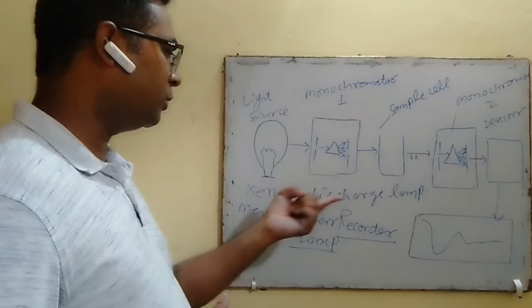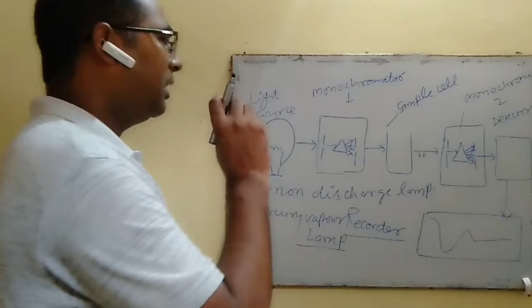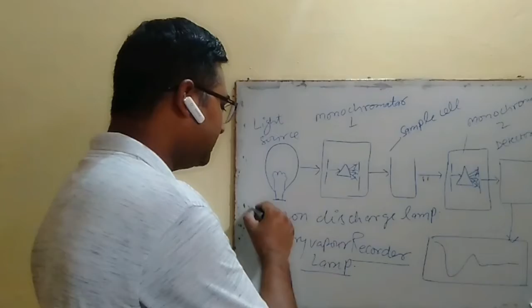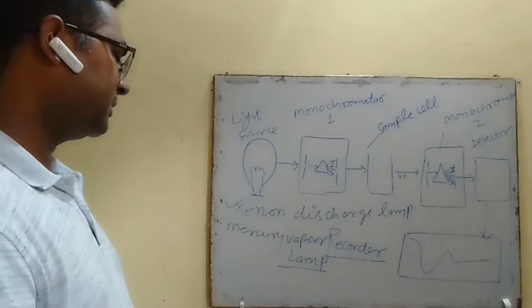The intensity emitted by the mercury vapor lamp is high as compared to the xenon discharge lamp, and where the intensity of the signal emitted by the substance is very low, in that particular case the mercury vapor lamp is used, because the intensity emitted by the xenon discharge lamp is less. So if the substance has sufficient fluorescent intensity, then the xenon discharge lamp is the lamp of choice. But in the case where the intensity emitted by the sample is very low, the mercury vapor lamp will be used as a source.